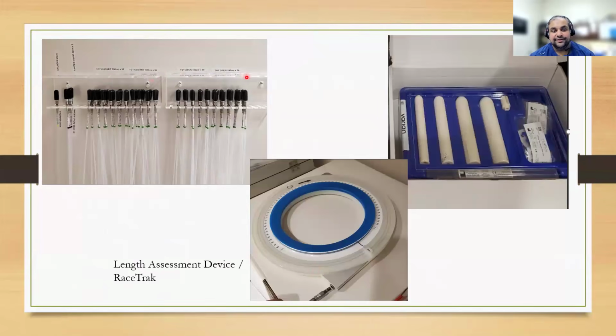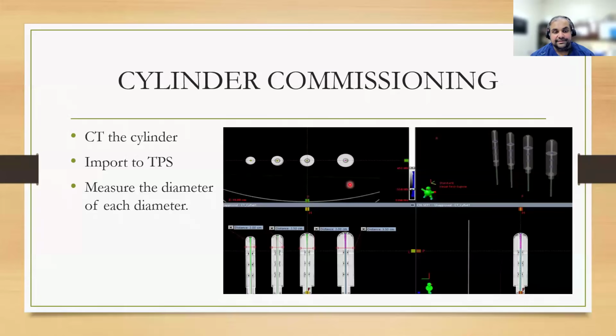We lay out our transfer guide tubes and label them so that everyone's on the same page on which transfer guide tube to use. And then you have your length assessment device. This is the cylinder kit that, in one of my previous clinics, when we started a brachy program, is what they had bought. So, you do a visual inspection. You can CT the cylinder, import it to your treatment planning system, and measure the diameter of each cylinder to confirm it matches what the vendor says. You can look at the 3D view to check for any internal damage. You can actually create your test plans and then deliver those plans also.